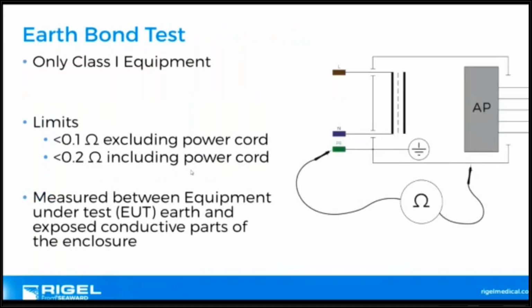So if you were to measure the earth bond, or ground bond, as is commonly known in other parts of the world, we need to make sure that we have a really good connection, almost zero resistance from your protective earth to any exposed metal. Because, and I'm drawing the picture, let's say this chassis around the medical device is conductive, and we've got a transformer here or some kind of power supply. Let's say this point here hasn't been screwed in properly. It manages to creep over to some exposed metal wire.